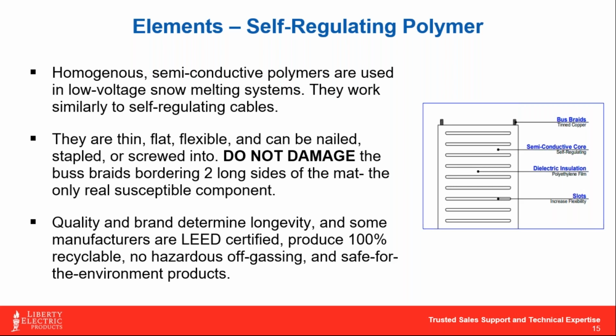The nice thing about these is that they're incredibly thin. They come in widths from 3 inches up to 12 inches maximum. One really nice feature is that during installation you can use a non-grounding fastener, anything galvanized like a staple, nail, or screw, and you can drive it right through this heating element and it will still continue to work. So it doesn't have the vulnerabilities some other cables have during installation. It can be used for both roof and gutter and sidewalk snow melting applications, but we'll get into its advantages and disadvantages further down the road.